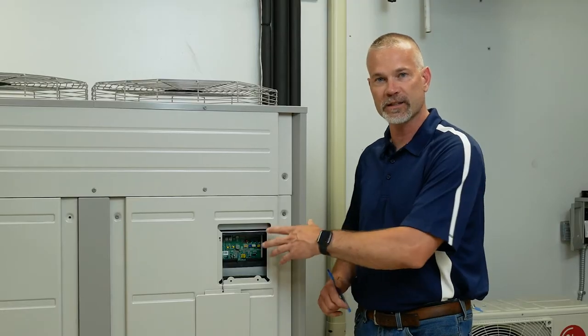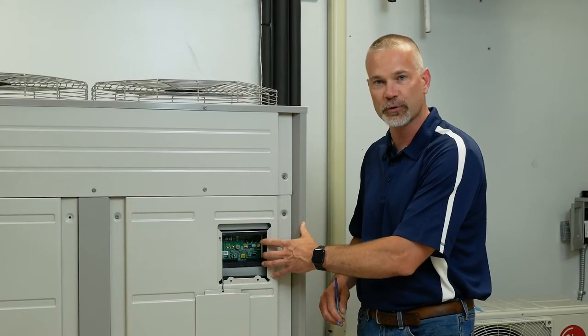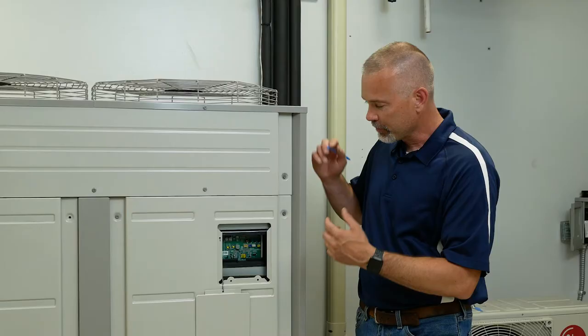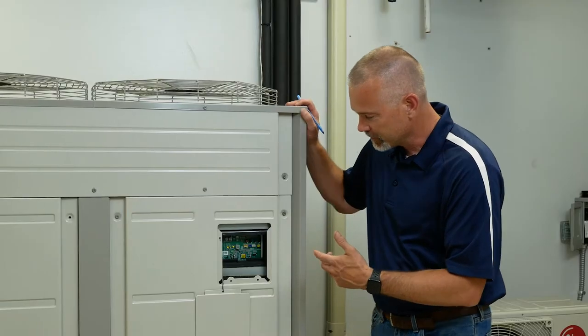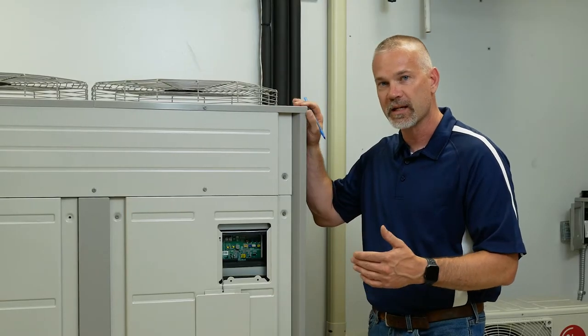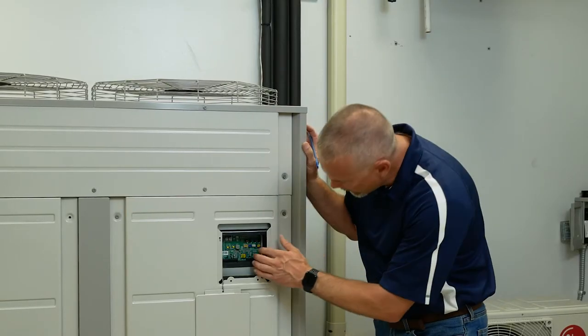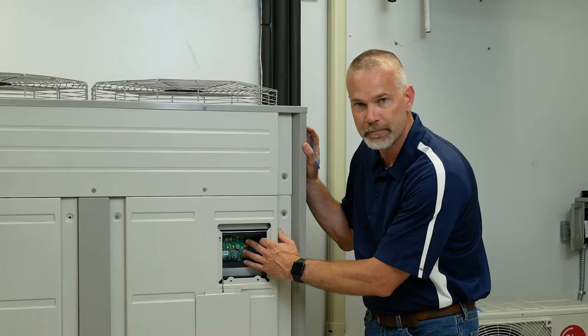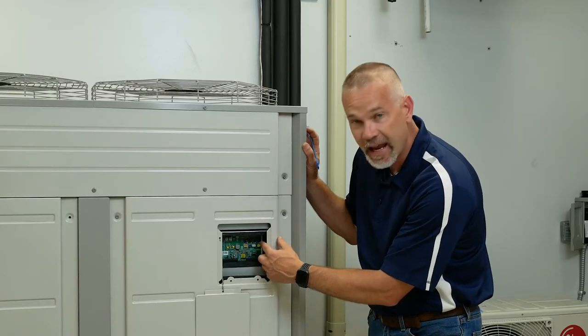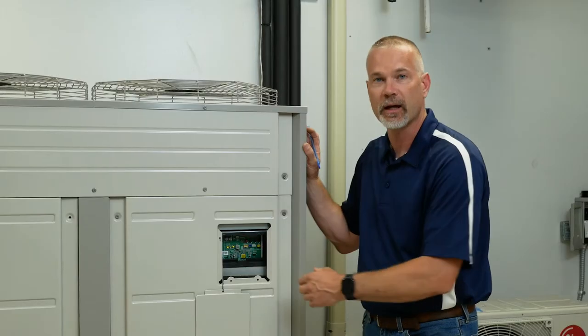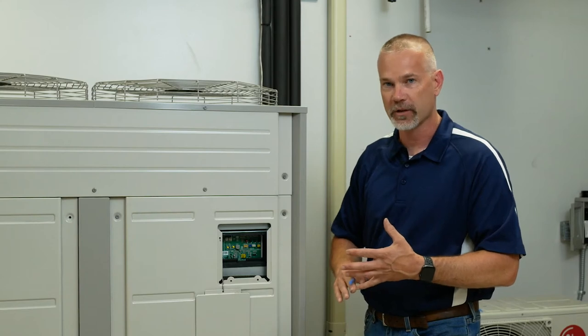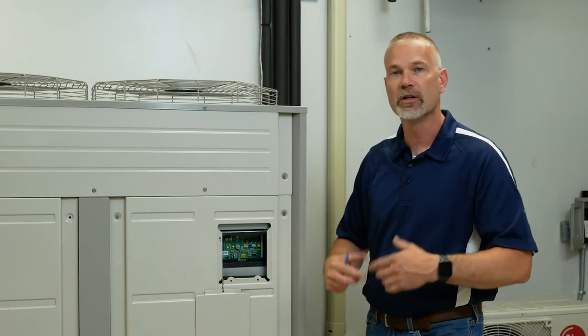It collects information about the number of units, capacity, and all the parameters for those indoor units and stores it at the outdoor. To do that process, we need to hit the red button on the outdoor main PC board. You'll see an 88 display on the board.